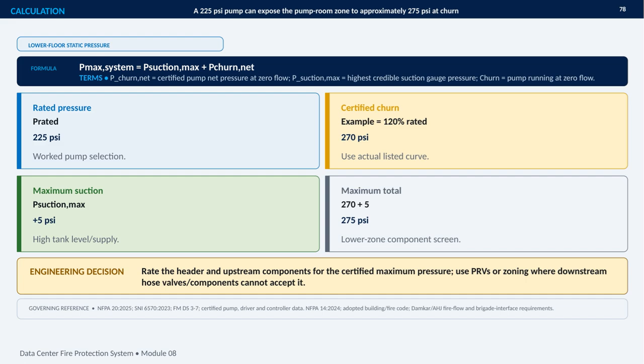In this worked example, the pump is rated at 225 psi, and the certified churn pressure is shown as 270 psi, or 120% of rated. We then add 5 psi for the maximum suction condition, such as a high tank level or elevated supply pressure. That produces a maximum total of 275 psi at the lower floor components. This value is the pressure that must be used to screen the header and upstream equipment. Any downstream hose valves or other components that cannot accept it may require pressure-reducing valves or a separate pressure zone. The design should be checked against the certified pump, driver, and controller data, along with the applicable NFPA, FM, SNI, building code, and authority having jurisdiction requirements.